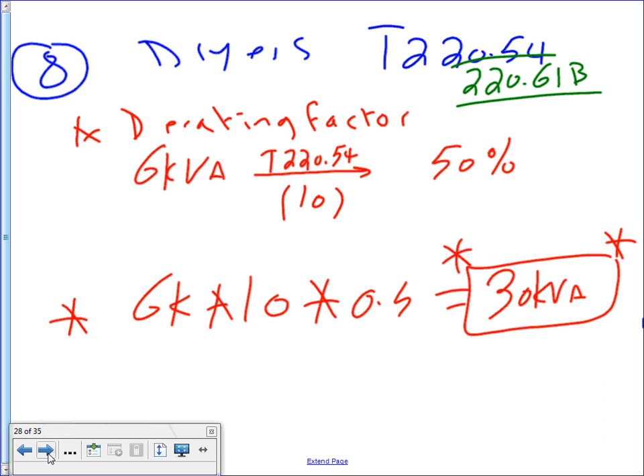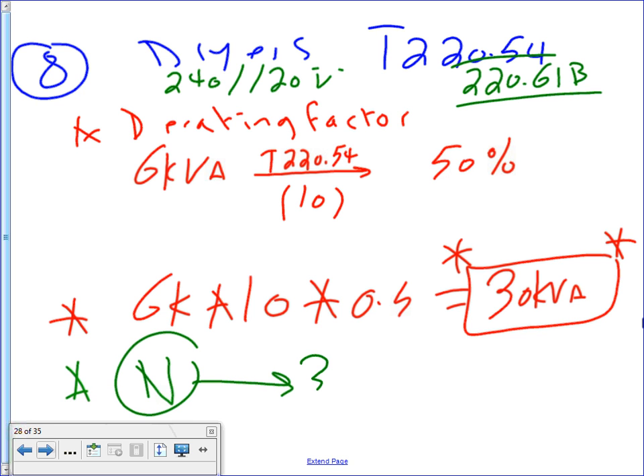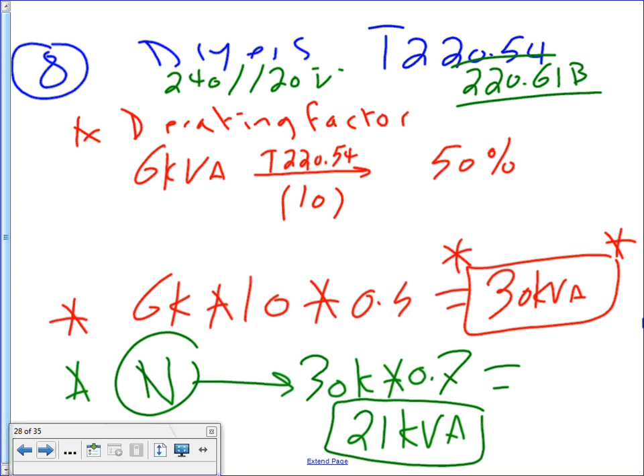All right, so next, dryers. Right here, it's a 240/120 volt system. That's why they count. You do the same thing for the dryers, guys. You take a step here. Here's my neutral. My neutral is 30K. Multiply this one by 0.7. That will get you a healthy 21 kVA. That's it. Can you guys see the same calculation? The neutral, you just take 70% of it.